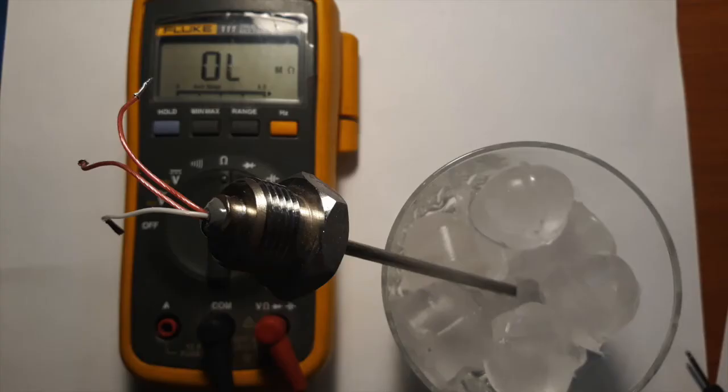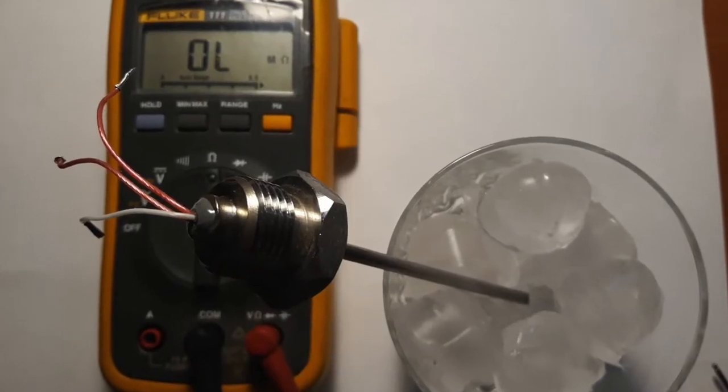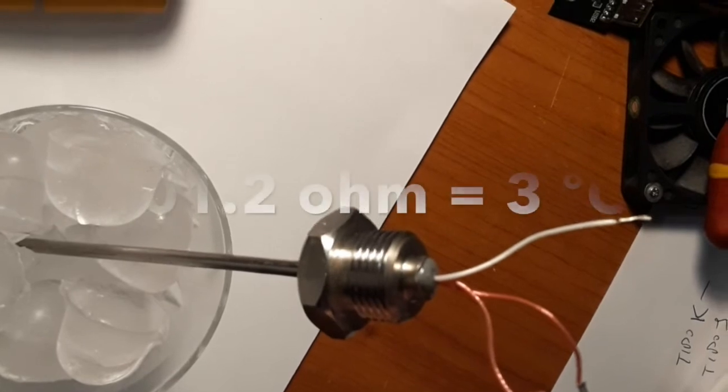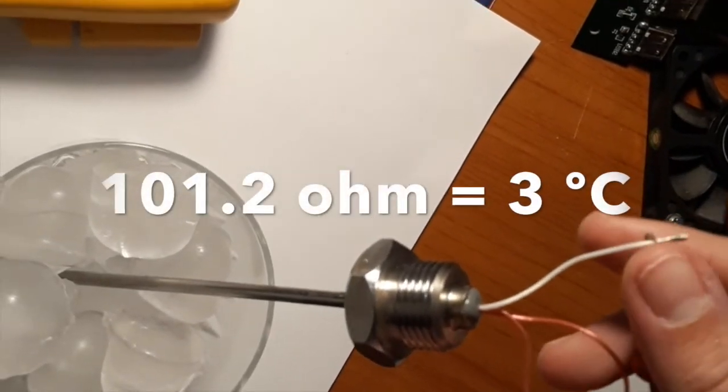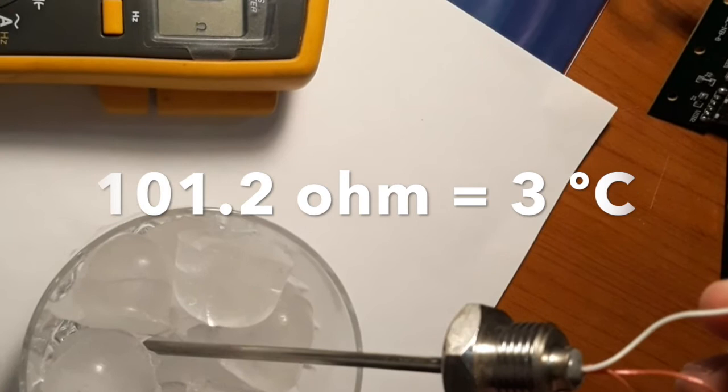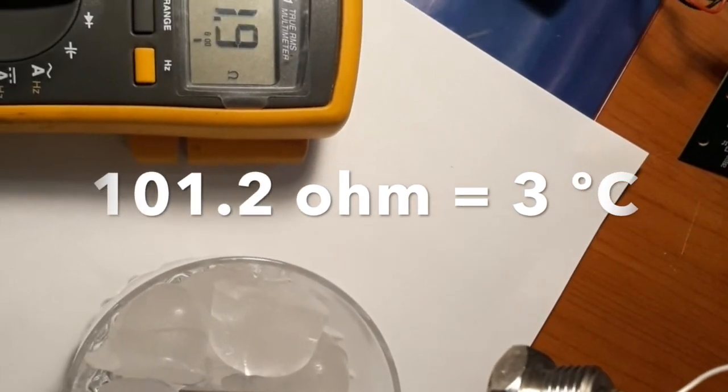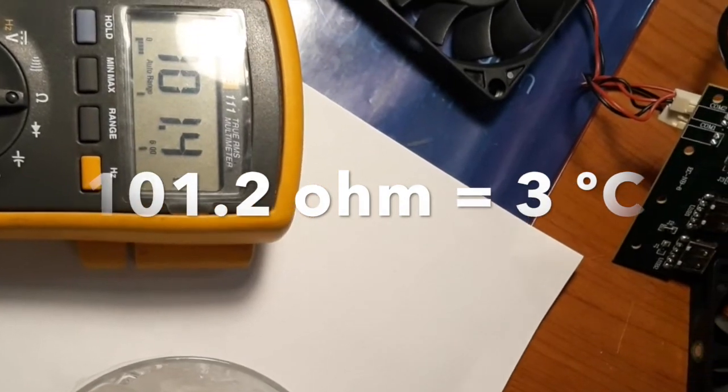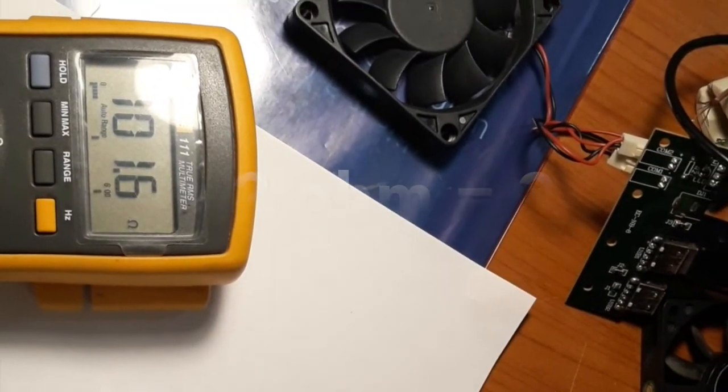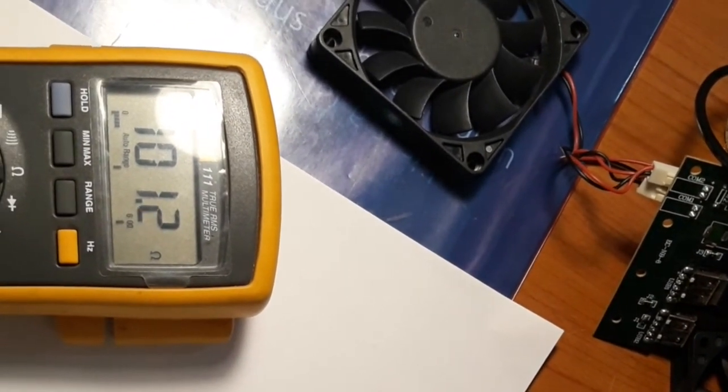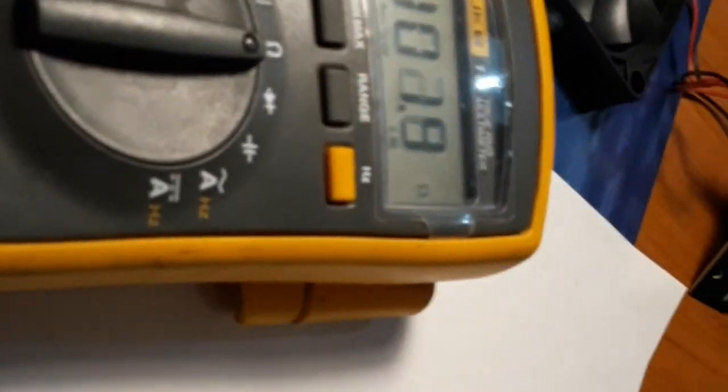PT100 thermoresistance calibration is used to check and find the sensor error limits, although these sensors normally have excellent accuracy. Some very specific factors, such as time of use, chemical changes in the wire, or changes in the crystalline structure of the platinum, may be directly responsible for causing the temperature sensors to lose their characteristic curve and, consequently, their precision.